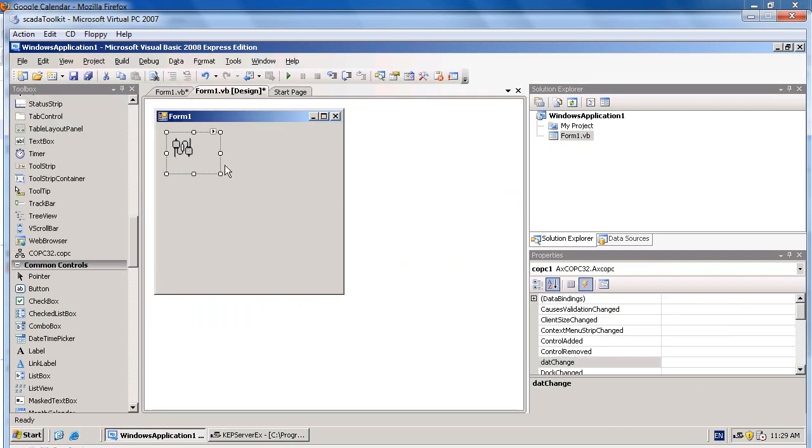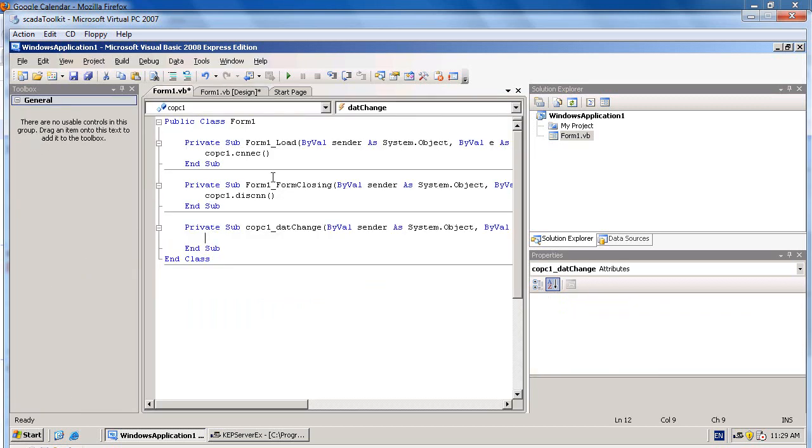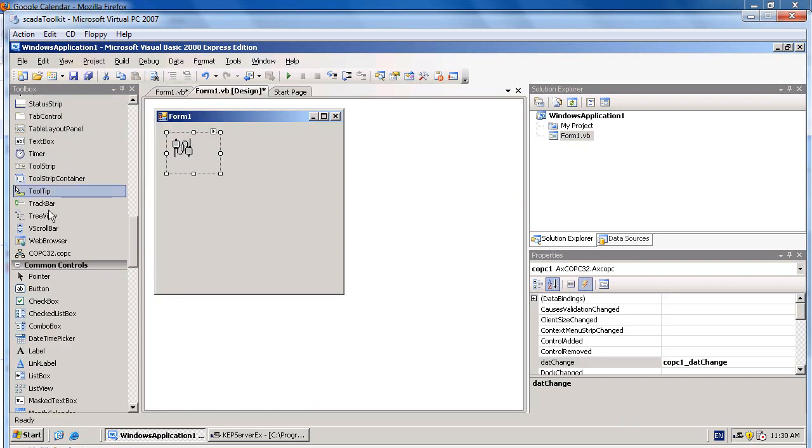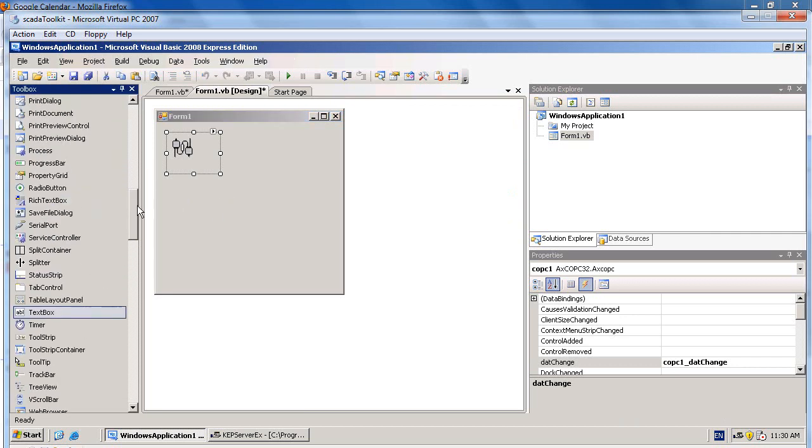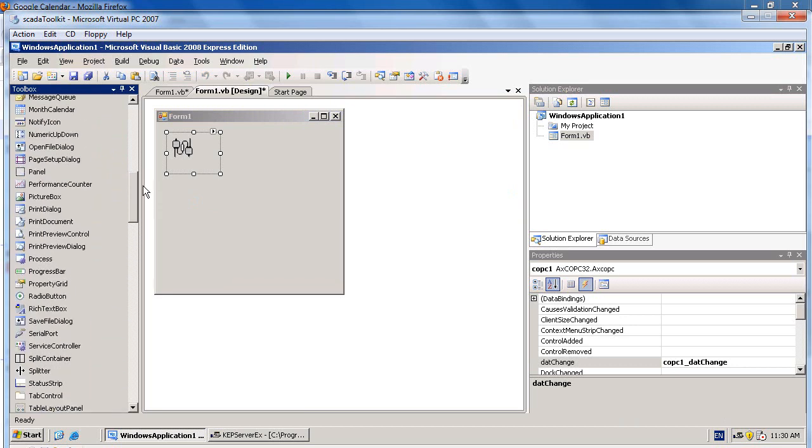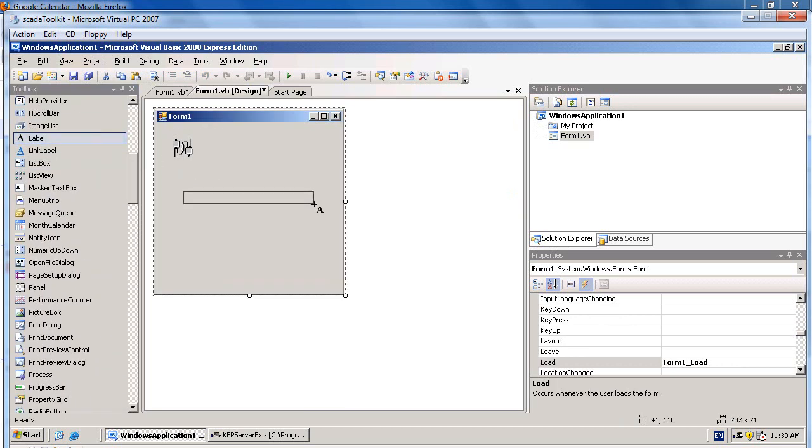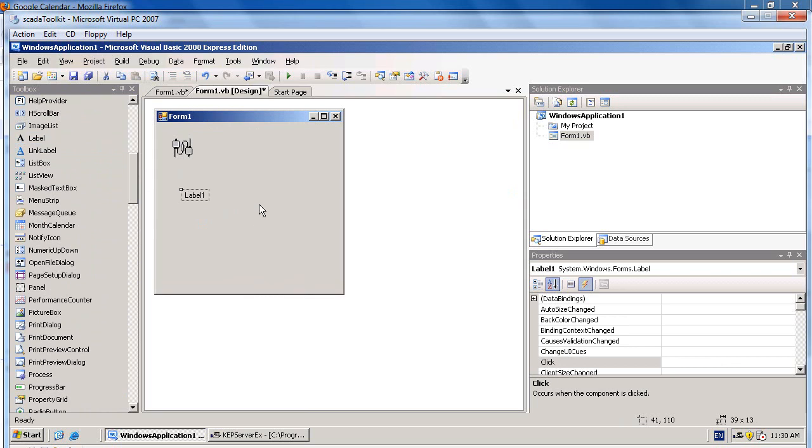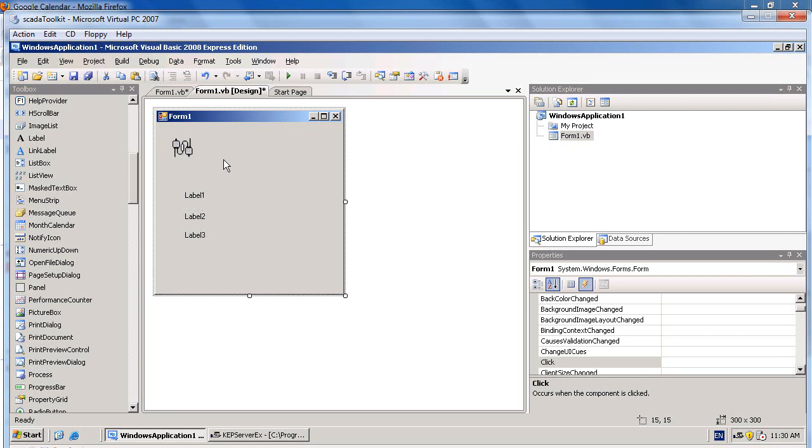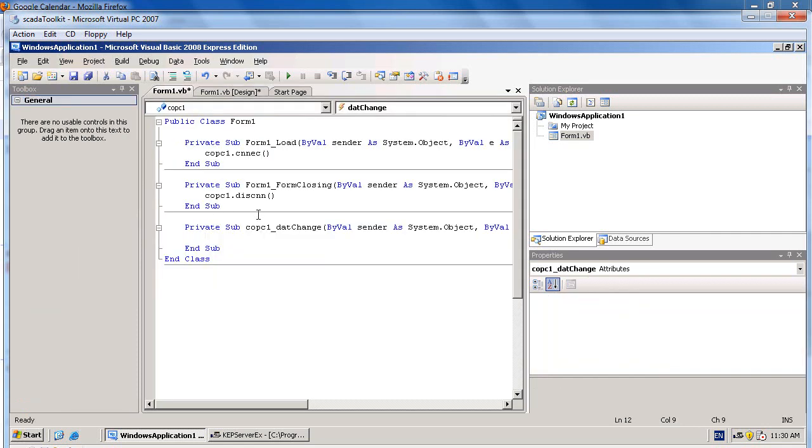When the data of OPC value has changed, we would like to show the value that changed into the form. We will show it on some textboxes or labels. In this example, I will use labels. Three labels. Then click on the COPC control. You will see Data Changed. This event will invoke when data of OPC tags has changed.